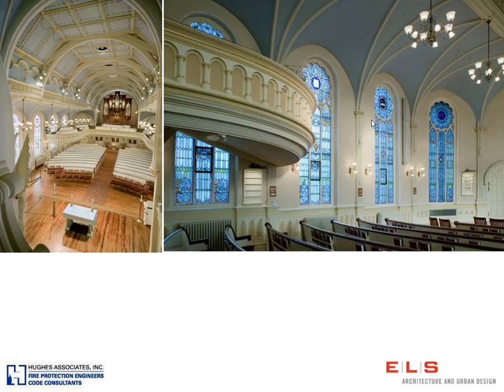And as you see, we really couldn't compensate for the fact that these historic windows had these mullions. It would have been very detrimental to the character-defining feature to provide them here, and to modify the windows, or even just to provide them here at all would be an impact on this archway around the window. And so we actually used computer modeling to demonstrate that with these sprinklers at the ceiling, we could still accomplish safe egress. These sprinklers would actuate, would cool the face of the windows, and occupants would be able to exit on the outside alongside of these windows and reach a public way before they would break. So these sprinklers were actually used to maintain a cooling effect on these windows to protect our egress way.